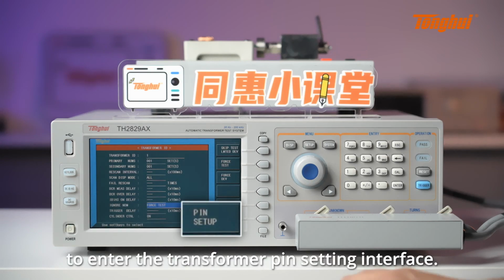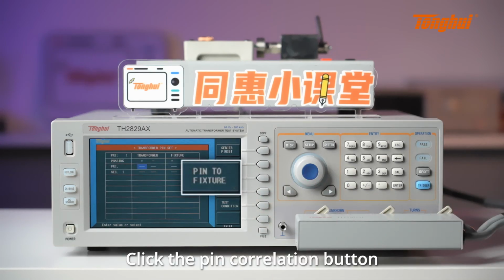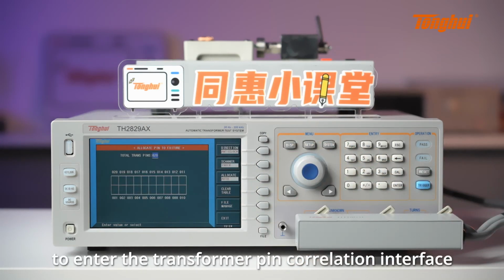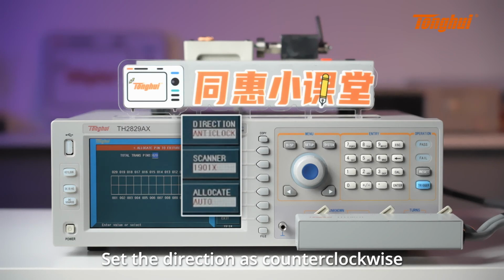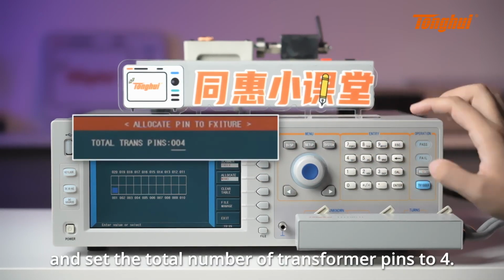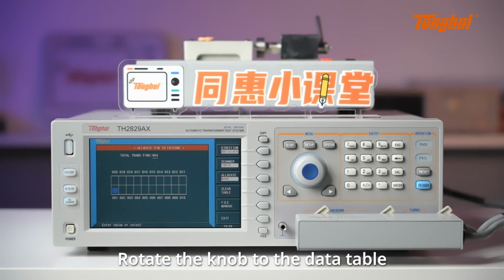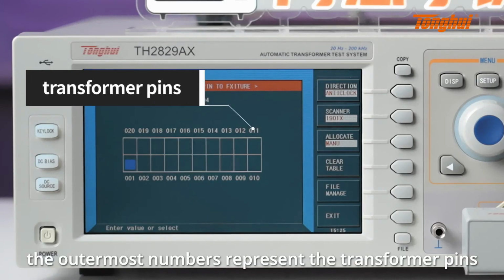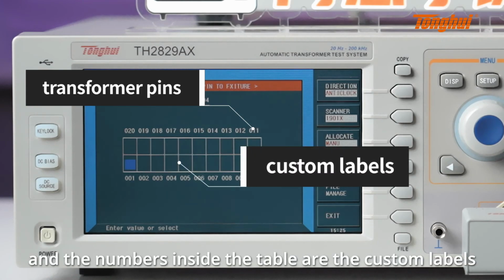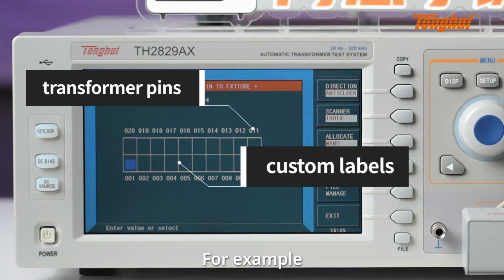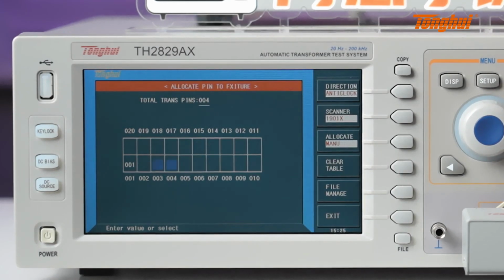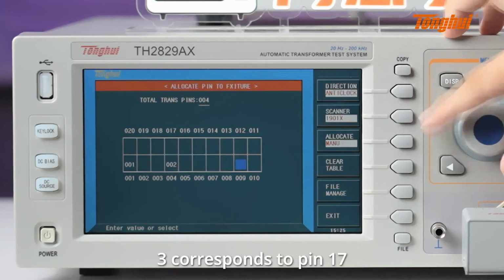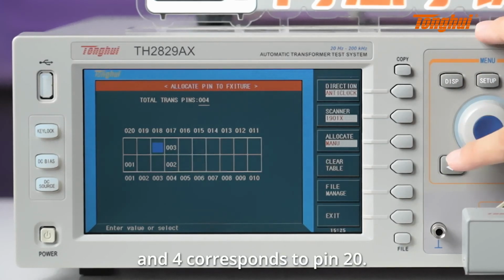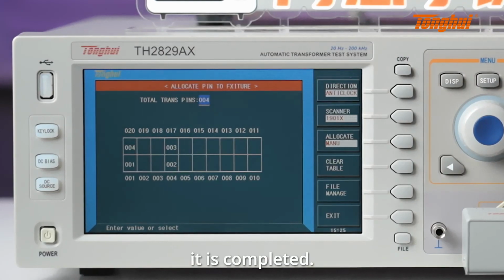Click Pin Setting to enter the transformer pin setting interface. Click the Pin Correlation button to enter the transformer pin correlation interface. Set the directions as counterclockwise, using the default values for scanning box, and set the correlation to manual, and set the total number of transformer pins to 4. Rotate the knob to the data table. The outermost numbers represent the transformer pins, and the numbers inside the tables are the custom labels. For example, 1 corresponds to pin 1, 2 corresponds to pin 4, 3 corresponds to pin 17, and 4 corresponds to pin 20. Once set, it is completed.